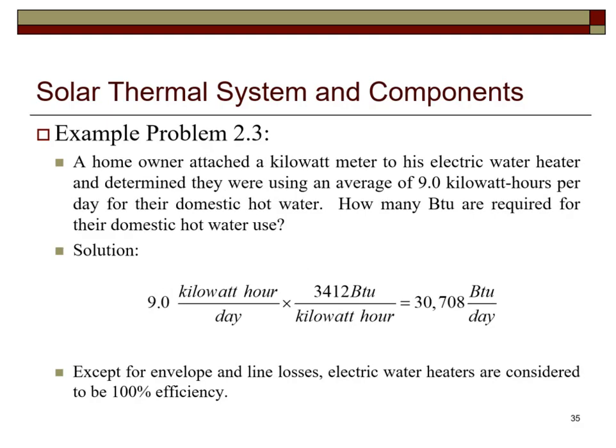Here we demonstrate the use of data logging on an electric water heater. In this case, 9 kilowatt hours per day are used to heat the water. Taking 9 kilowatt hours per day multiplied by 3,412 BTUs per kilowatt hour gives us 30,708 BTUs per day.